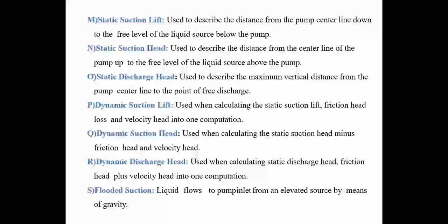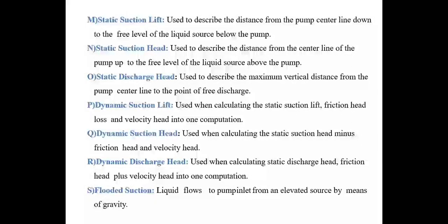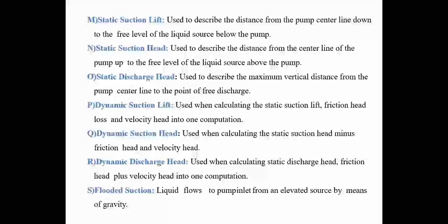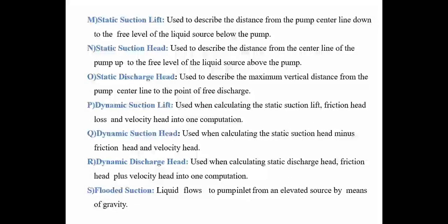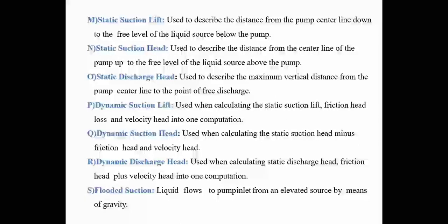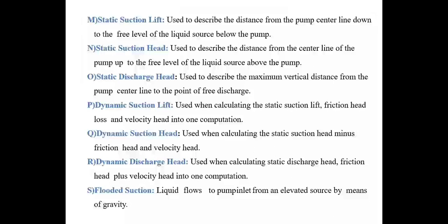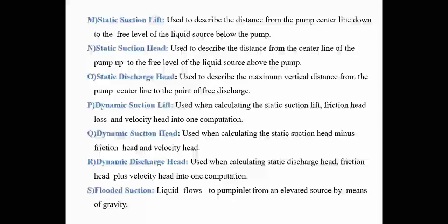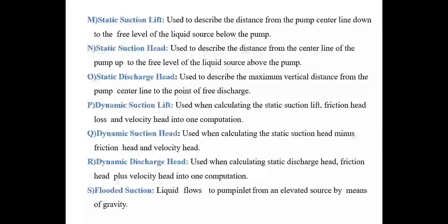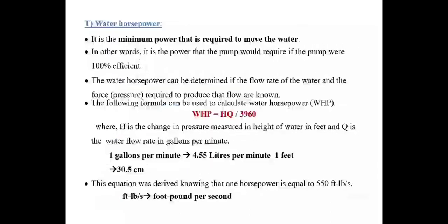Now another term is flooded suction. Flooded suction is the condition in which the liquid flows to the pump inlet from an elevated source by means of gravity. If the water source is above the pump, then that type of suction is known as flooded suction. For example, if there is a tank at the upper end of a hill and we are pumping water to the lower end, then that case is known as flooded suction.